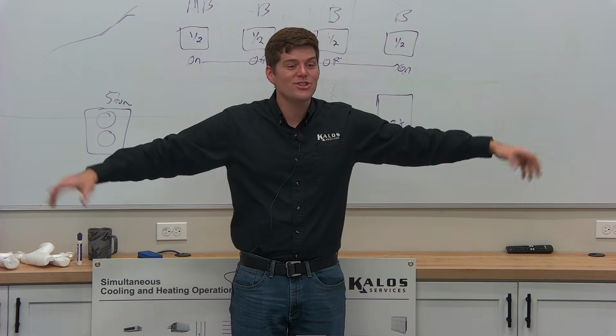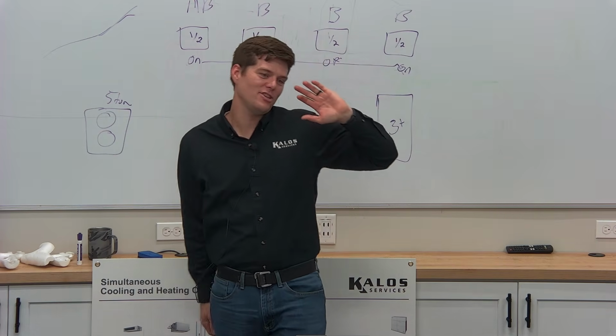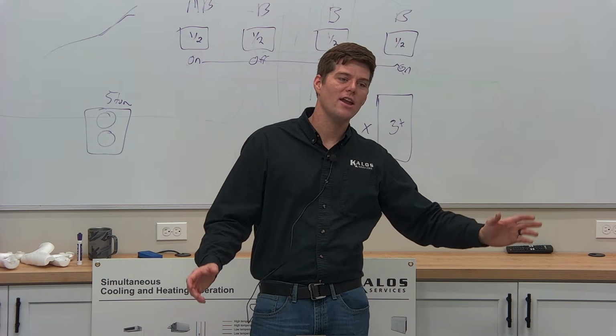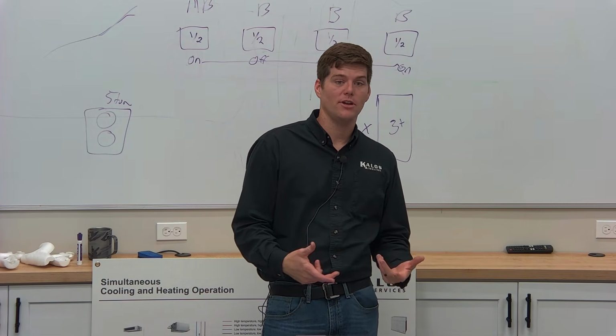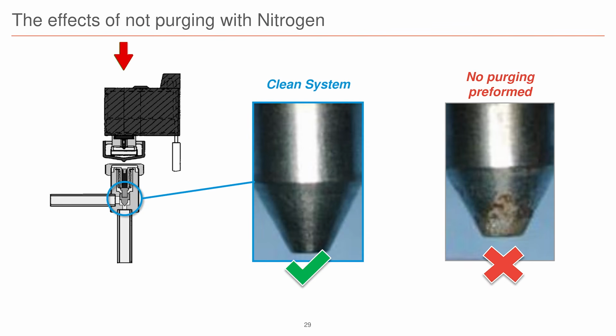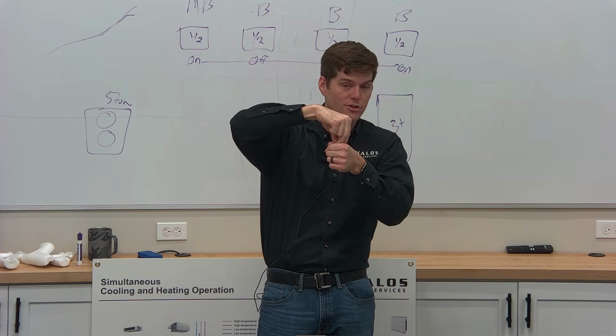Okay, oxidation, sure, yes, it's going to get stuck in the system. It's going to cause all this kind of damage, but why does it also matter on VRF? We have an electronic expansion valve. This is the needle inside of the electronic expansion valve. As you can see on the left-hand side on our clean system, it is extremely polished, it's clean, right? That seats right down here in a perfect seal, no refrigerant leak by.